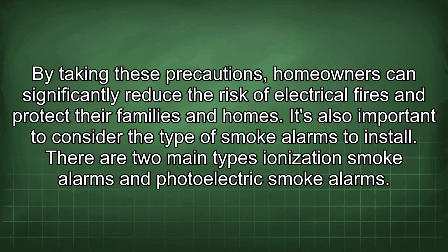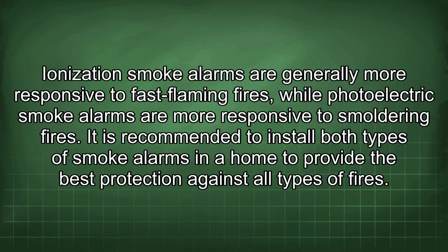It's also important to consider the type of smoke alarms to install. There are two main types: ionization smoke alarms and photoelectric smoke alarms. Ionization smoke alarms are generally more responsive to fast-flaming fires, while photoelectric smoke alarms are more responsive to smoldering fires.